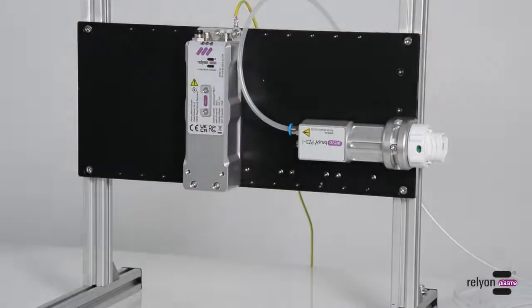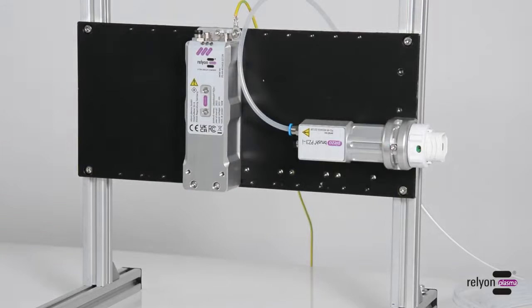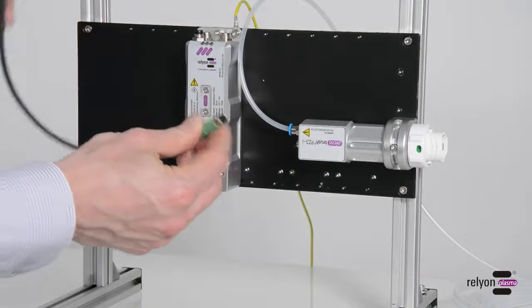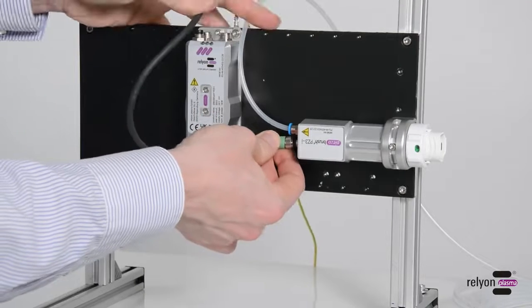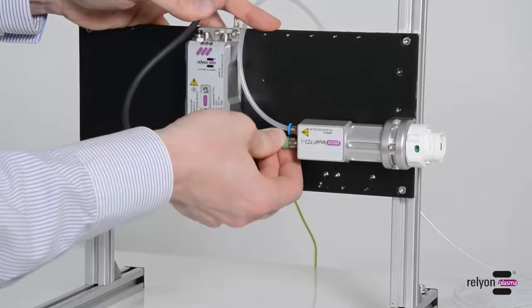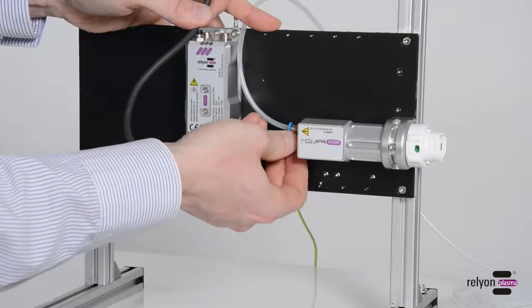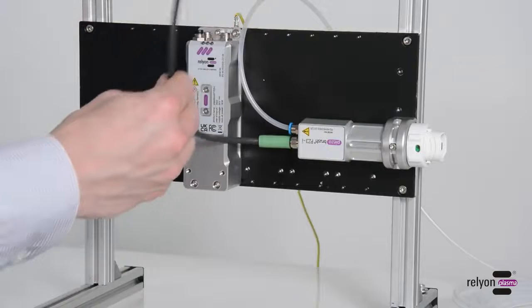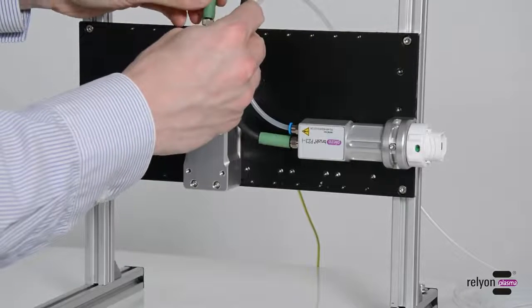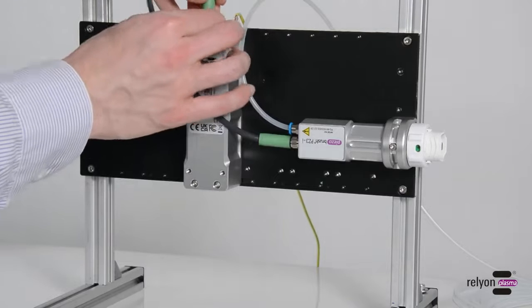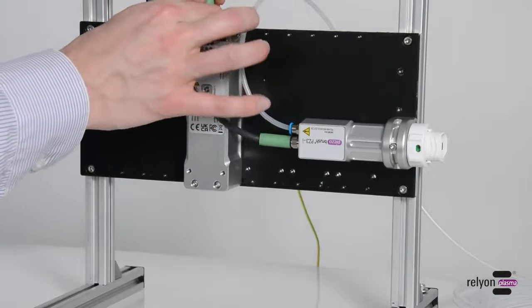The supplied cable has a length of 0.3 meters. If necessary, longer cables can be used. Due to the fact that with longer cable lengths, the EMC is strongly depending on the actual integration, we recommend an EMC test in the final setup. The other connections are made as for the standard setup.